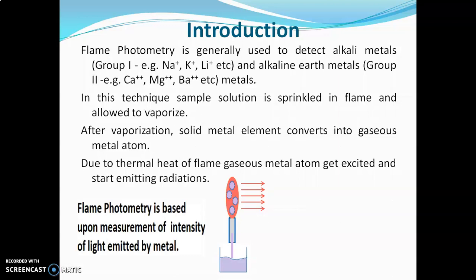This emission of radiation is the basis of flame photometry. Flame photometry is based upon measurement of the intensity of light emitted by the metal. The color of the light — meaning the wavelength of the light — tells us which metal is present, and the intensity of the light tells us how much metal is present.